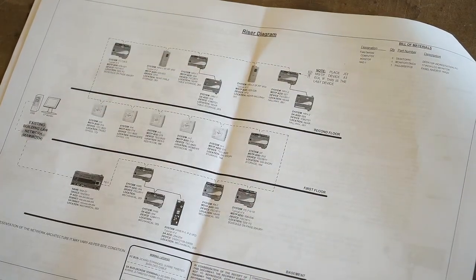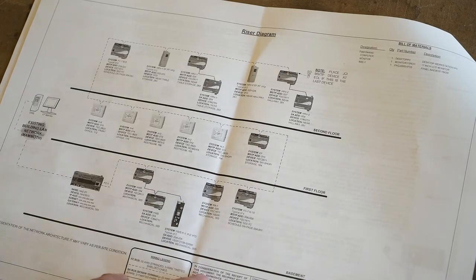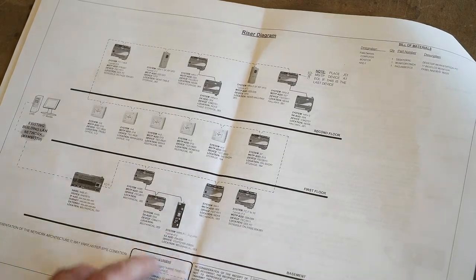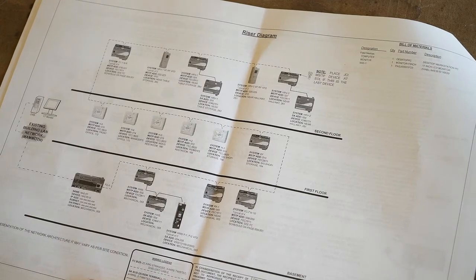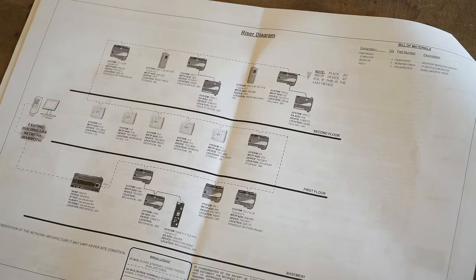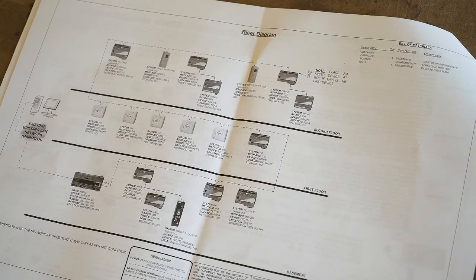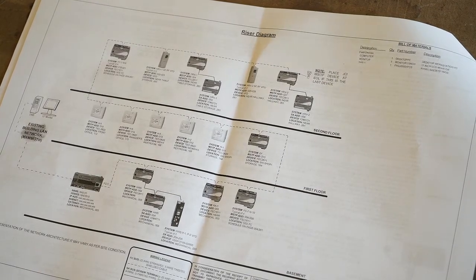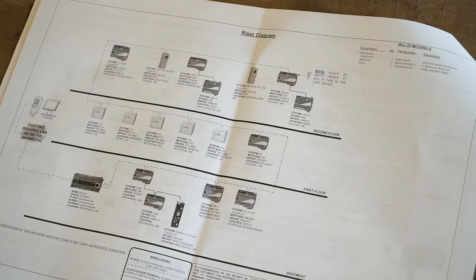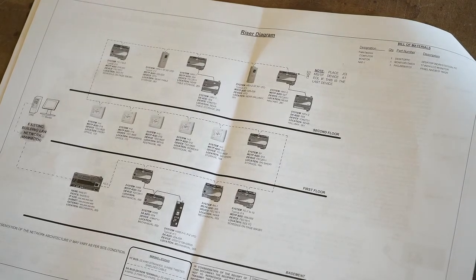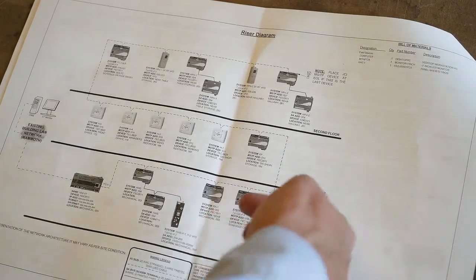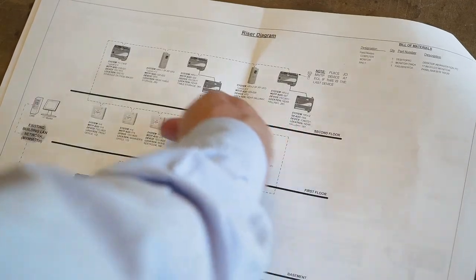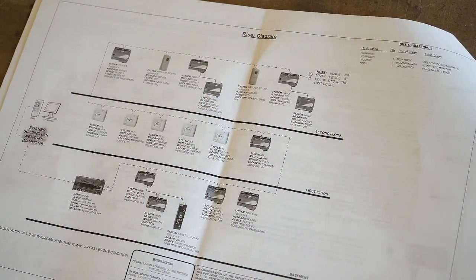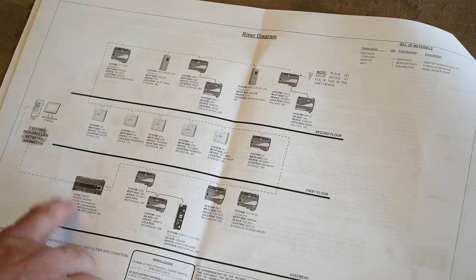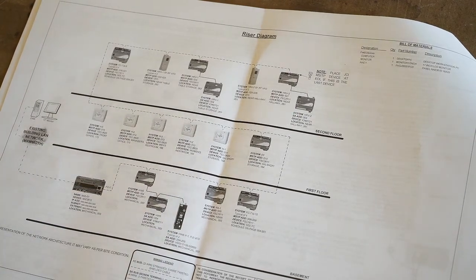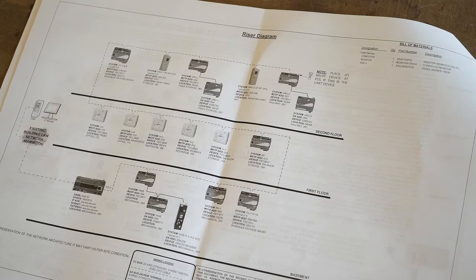And this is all on the program? These will all be in the O&Ms. Oh, okay. So you guys will actually get copies of these drawings. Okay. But as far as figuring out which one is missing? When you look on the front end, you'll have red X's on the ones that you aren't communicating with. Okay. So then you can reference that to the drawing. That'll tell you whether it's between basement and first floor and second floor, or if the whole trunk's down, then you probably have some type of an issue coming off the NAE. Okay.